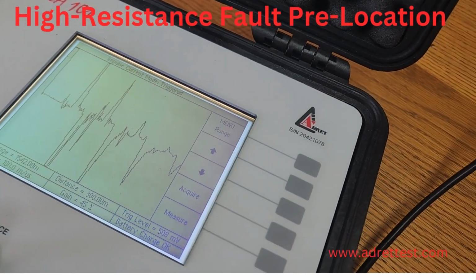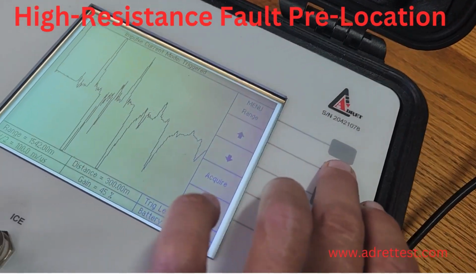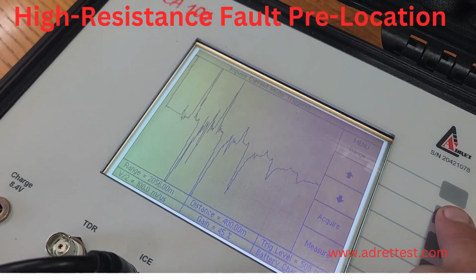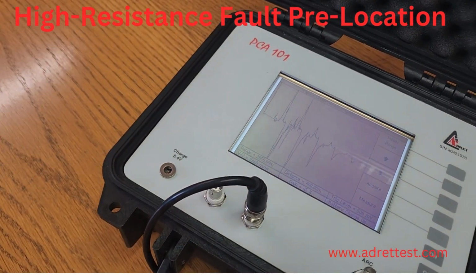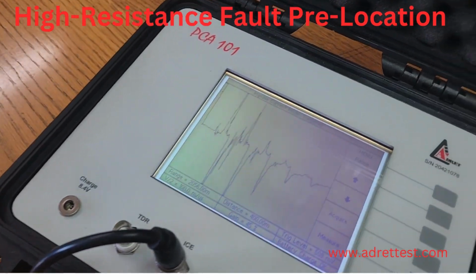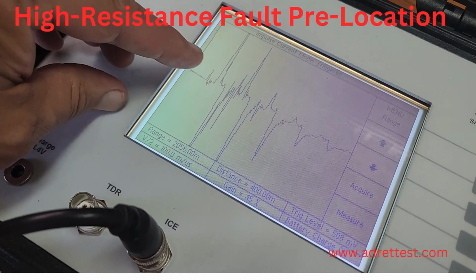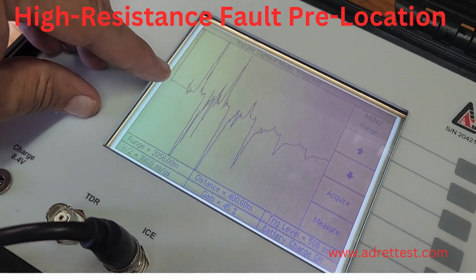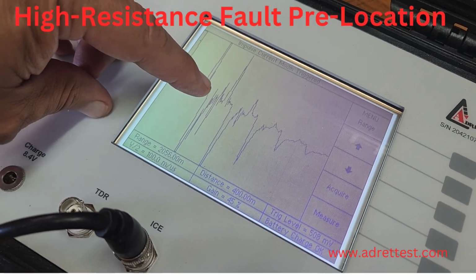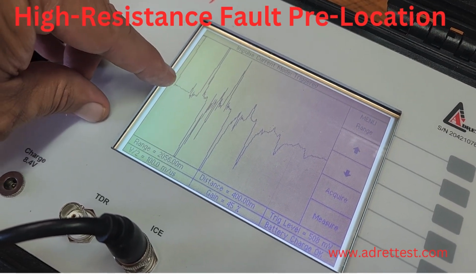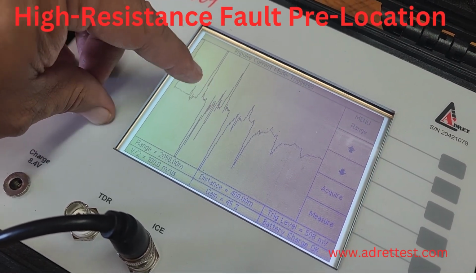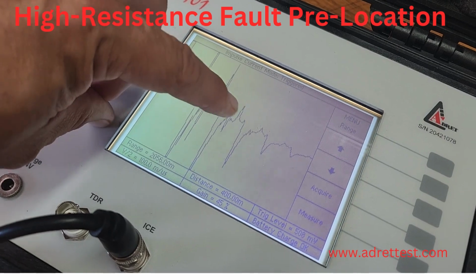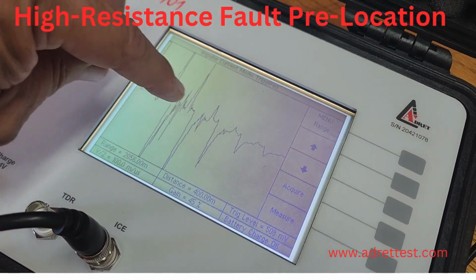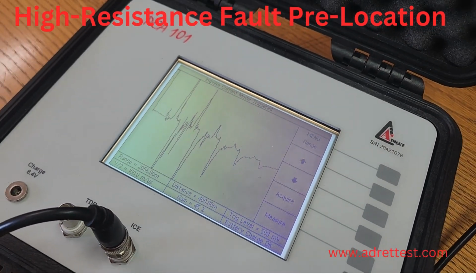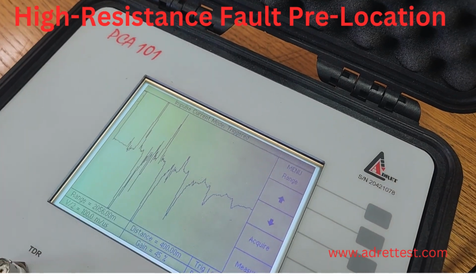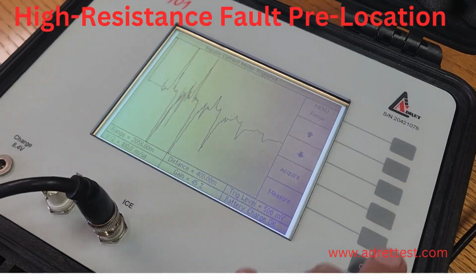Now, you can still change the range a bit when it's done shooting. Just want to make the machine safe. Okay, now if you look at this graph, the pulse is moving away from us down the cable to where the fault is, coming back. Going away from us to where the fault is, coming back. Each time it's losing some energy. So with that intervals, now you know that that is the fault.